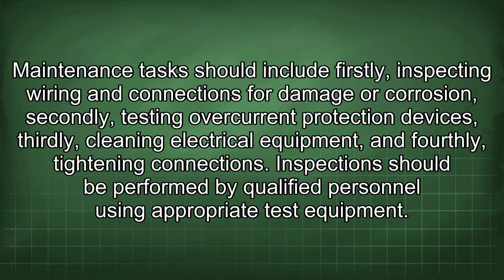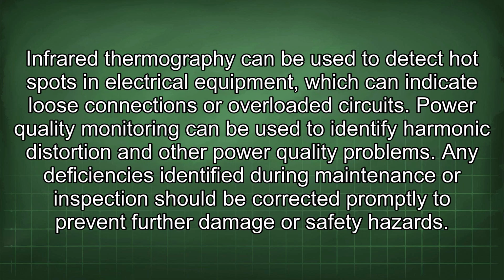Maintenance tasks should include firstly, inspecting wiring and connections for damage or corrosion, secondly, testing overcurrent protection devices, thirdly, cleaning electrical equipment, and fourthly, tightening connections. Inspections should be performed by qualified personnel using appropriate test equipment. Infrared thermography can be used to detect hot spots in electrical equipment, which can indicate loose connections or overloaded circuits. Power quality monitoring can be used to identify harmonic distortion and other power quality problems. Any deficiencies identified during maintenance or inspection should be corrected promptly to prevent further damage or safety hazards.